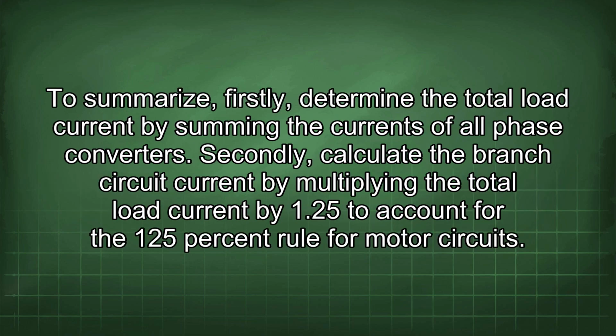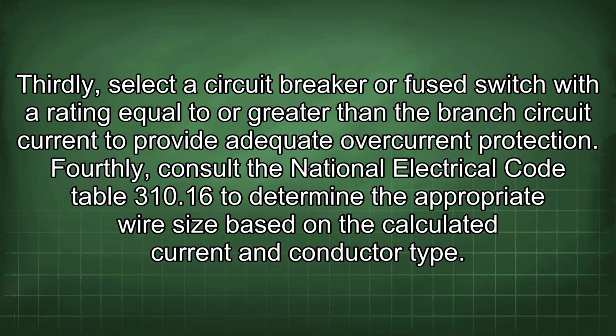To summarize, firstly, determine the total load current by summing the currents of all phase converters. Secondly, calculate the branch circuit current by multiplying the total load current by 1.25 to account for the 125% rule for motor circuits. Thirdly, select a circuit breaker or fuse switch with a rating equal to or greater than the branch circuit current to provide adequate overcurrent protection.